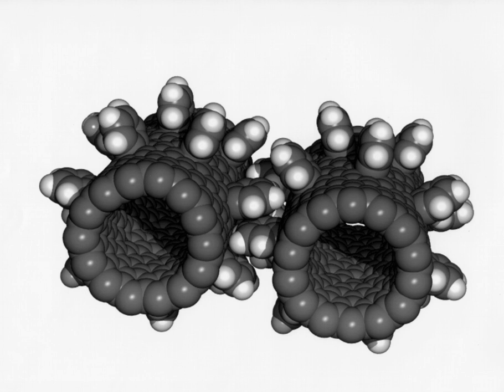Nanofiltration is a relatively recent membrane filtration process used most often with low total dissolved solids water such as surface water and fresh groundwater, with the purpose of softening, polyvalent cation removal, and removal of disinfection by-product precursors such as natural organic matter and synthetic organic matter.